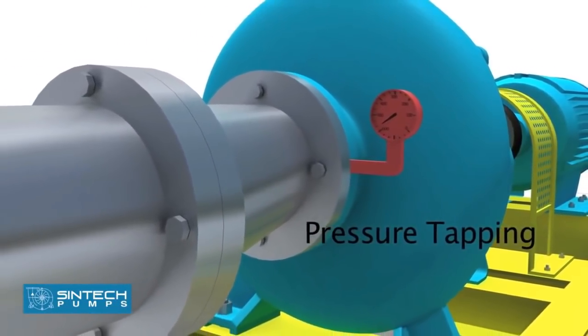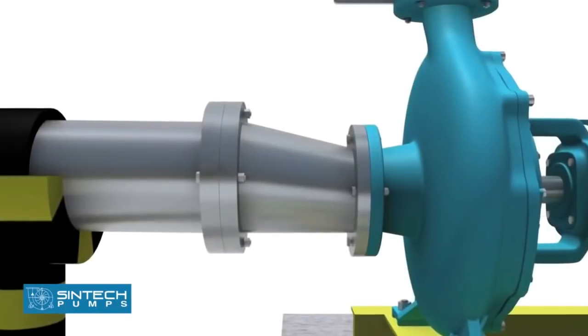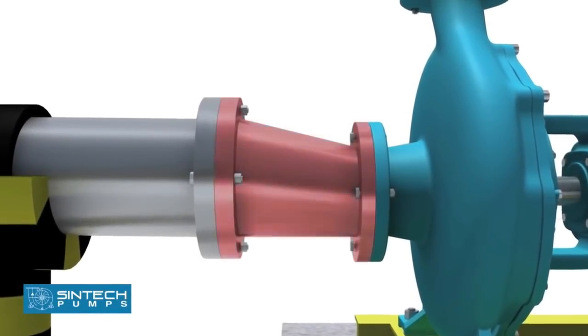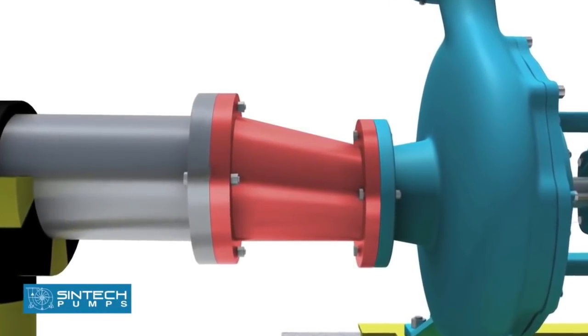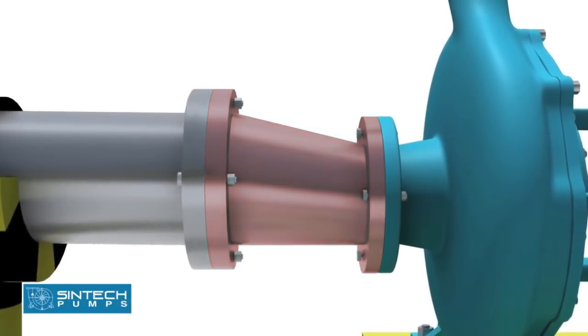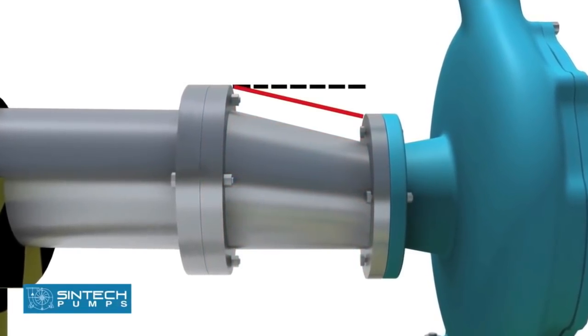There should be a tapping provided for installing a pressure gauge in the suction line. The reducer joining the straight length of the pipe in the pump line should be an eccentric reducer with the inclined side of the reducer as the top side.